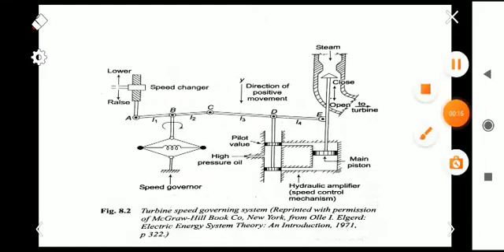This is the turbine speed governing system we have already learned in the previous videos. The flyball speed governing is a very important part here — as the speed increases, the flyballs move outwards. In effect, point B moves downwards, the lower pilot valve opens, and high pressure oil flows through this path to the main piston, moving it upwards and reducing the steam flow.